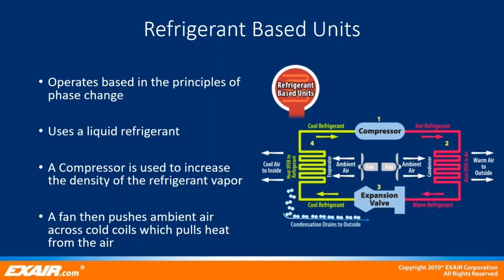Now, refrigerant-based units. All air conditioning systems utilize a specific material that undergoes a phase change process. That material, also known as a refrigerant, is contained within the tubing throughout the air conditioning system. The refrigerant is pulled into the system's compressor in the form of a warm vapor after leaving the evaporator coil. The compressor increases the density of the incoming refrigerant vapor, causing it to increase in pressure and temperature.